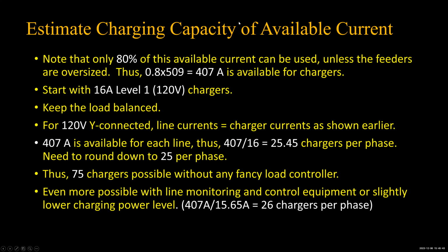But let's take a look at what else we might be able to do. Here's a Q&A. Let's see what we got. Won't you also need to apply a power factor to the existing load since you are getting kW as demand from the power company? You know, that's interesting because NEC says you can use kWs. And yeah, that's a good point. But that's where the 125% comes in pretty handy. Because if you're taking as your load 125% of the kW demand, then that gets you down to a power factor as low as 0.8, and it's probably not that low. So I guess it is kind of taken into account with the 125% number. Maybe that's why they put it there. I never asked him. That could be.